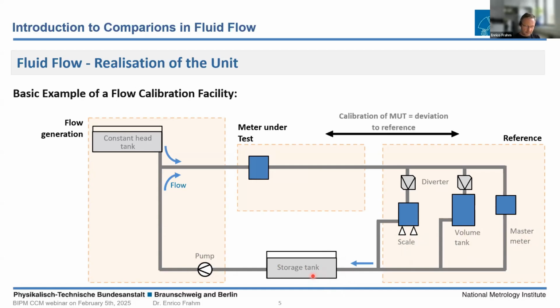And the calibration gives a result as the deviation between the meter under test and the reference. And the transfer standard itself has to be installed at the same place as the meter under test.